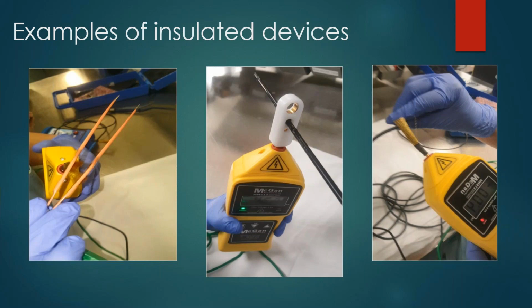This one was actually pretty bad. This was more of a test to show an example of insulation testing, but as you can see, it's pretty obvious that it was almost like it was chewed up. What happened was this got stuck in the blades of the washer, and it actually damaged it pretty bad. The last video was something that we really don't see technicians doing in the department, which is testing the bipolar, monopolar reusable cords that are in their laparoscopic trays and robotics or whatever it may be. So this is another area definitely that can be improved on, and I will show you some accessories that could help with that.